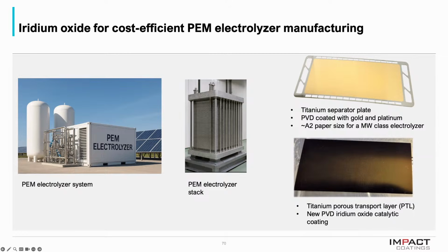To the right-hand side here, you have 2 components. On the top, you have a separator plate made of titanium. This is usually plated or coated with gold and platinum. It's about the size of an A2 paper for a megawatt class electrolyzer. And on the bottom, you have a titanium porous transport layer. It's kind of like a titanium sponge that is flat, you could say. And these we routinely coat. The main purpose is to provide electrical conductivity that should be stable throughout the lifetime of the stack. But to add further value, we move into the PVD iridium oxide, and this coating is catalytic, and it opens up a new field for us.